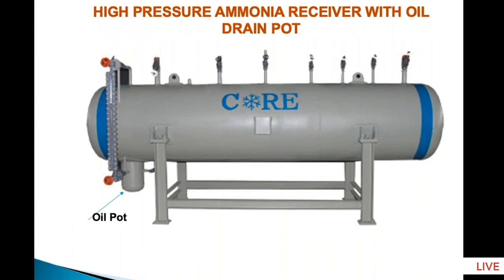This receiver, if you see, has an oil pot, because whatever oil escapes from the oil separator comes to the system, and we need to further remove that oil from the system. So there is an oil pot, again for removal of oil, and these are the various nozzles on the receiver, and also there is a gauge glass. This gauge glass indicates how much ammonia or refrigerant you have stored inside the receiver. The recommended practice is 75 to 85%.